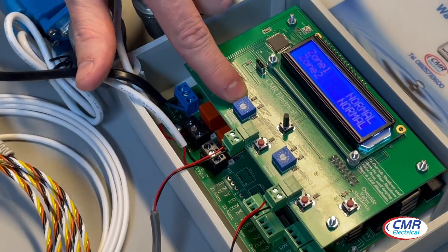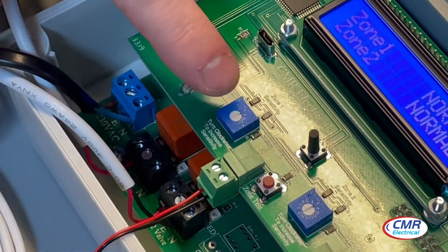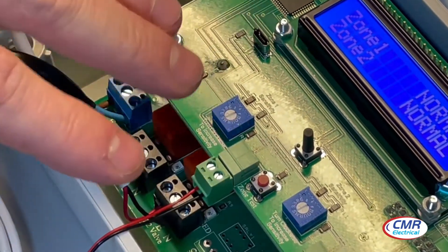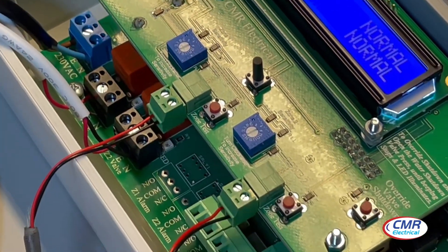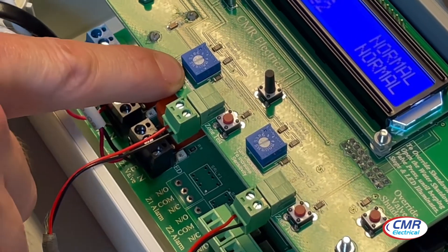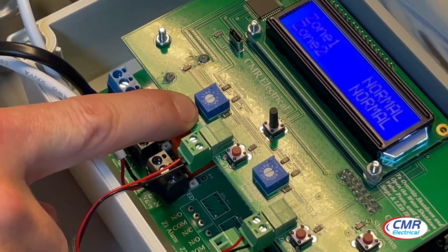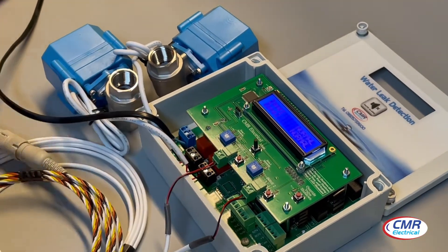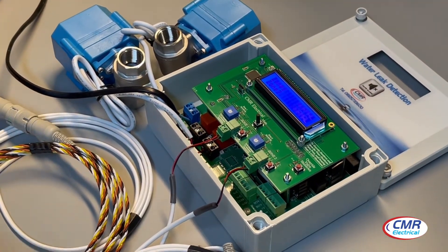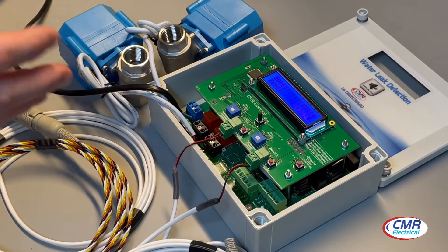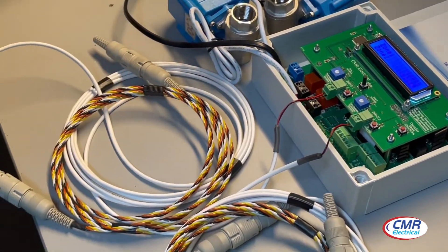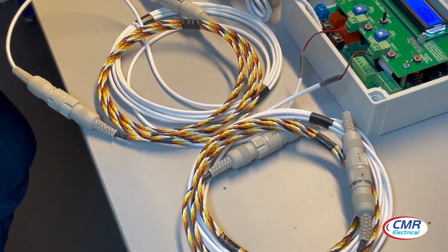These blue pots here are the sensitivity adjustment pots. You get one per zone, so if you have a two-zone system you will have two. You turn it anti-clockwise to desensitize it and clockwise to sensitize it. Depending on the areas, if you have a slightly damp area that's triggering your alarm, you can desensitize that zone to stop the alarms from occurring.